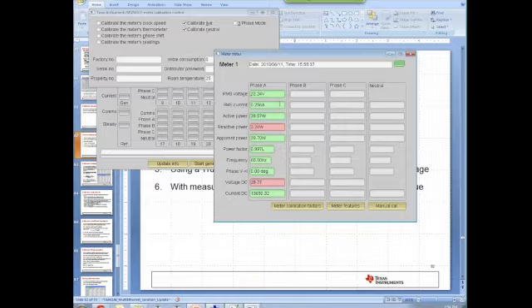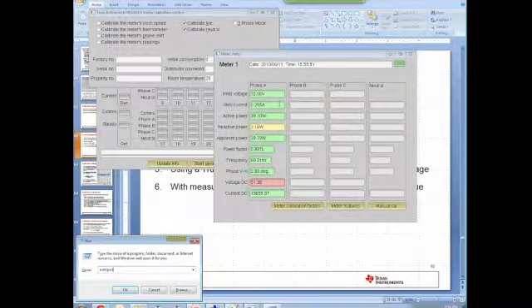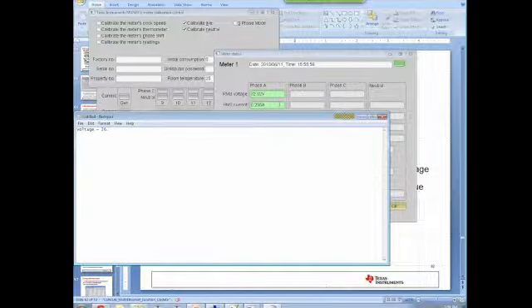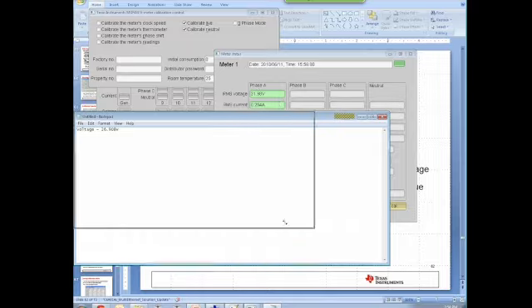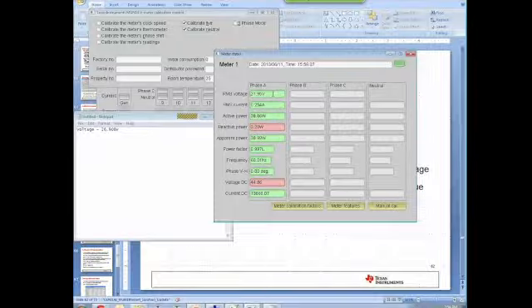So mine coming in, if I can get a connection on here, mine is 26.995 volts, which is obviously different than what my meter's reading up on the screen. So whenever you measure that voltage, make sure you mark it down somewhere. Open Notepad and just write it down, because that's the point we're going to calibrate to. 26.908 is where it's stabilized. So that's the voltage coming into the meter here. And as you can see, the RMS voltage here is clearly incorrect.